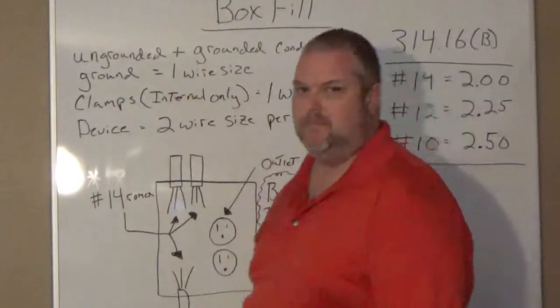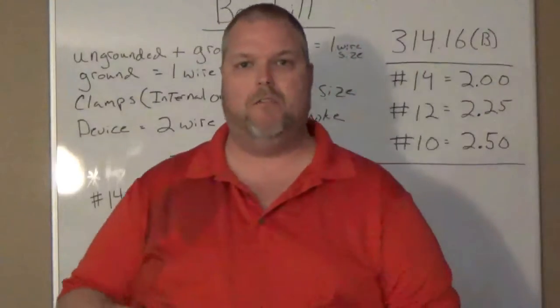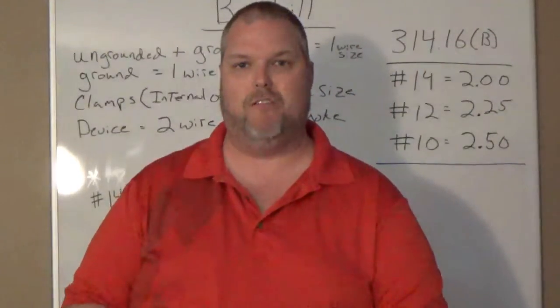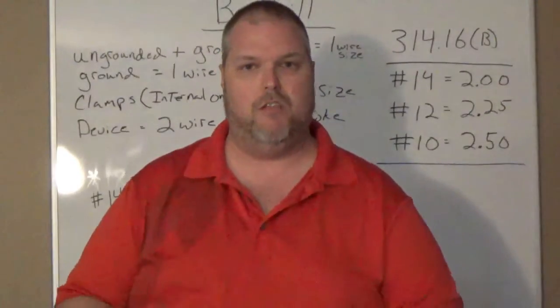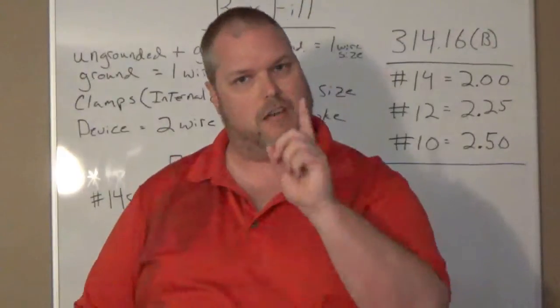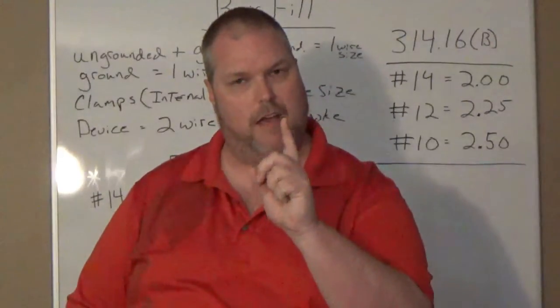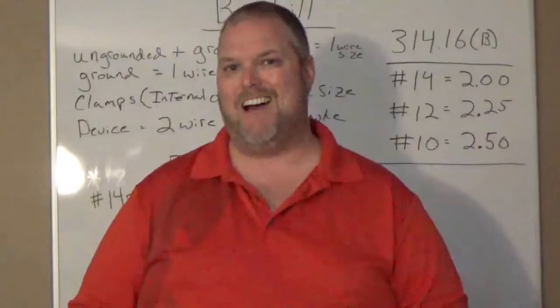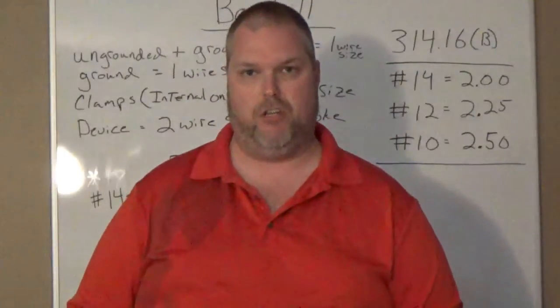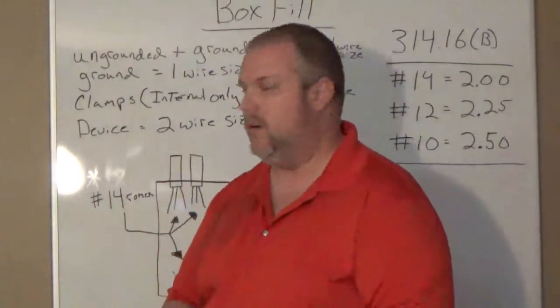The ground. You can have one ground. You can have two grounds. You can have three grounds. You can have 10 grounds. The ground in a box fill calculation is counted as one. It's the largest size ground conductor that you're going to use. I'll explain that more.